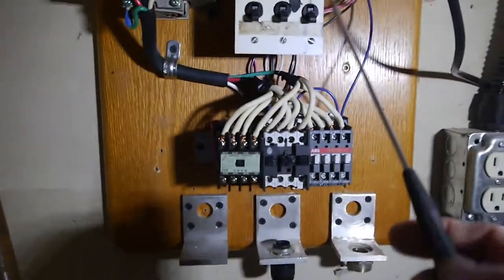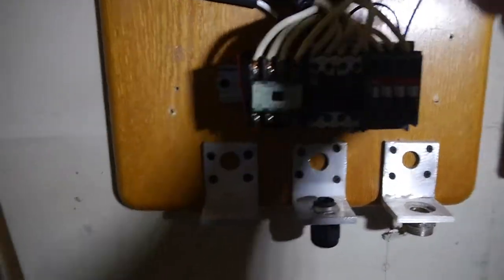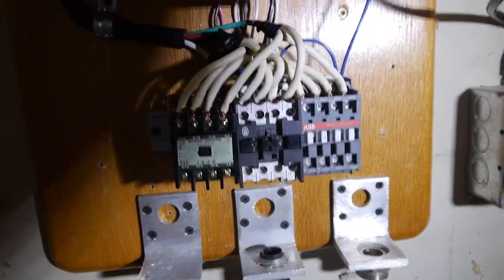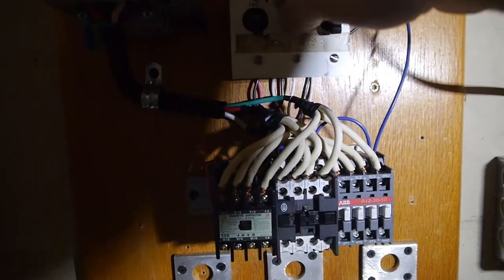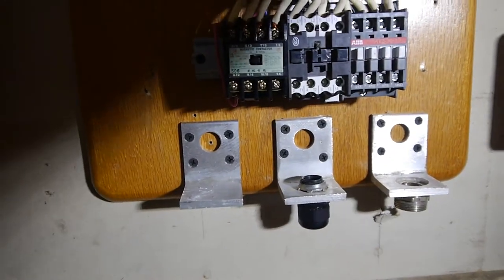Now let's see if we can get this motor contactor to close. Perfect. This one, middle one, perfect. Oh, that one's not. Something get loose. Oh, yep, there it is. Not sure if you can see back there. I don't know where it, right there, came off the terminal.